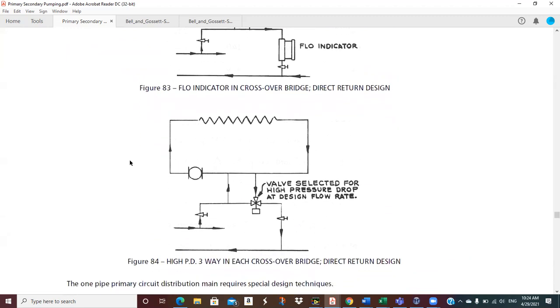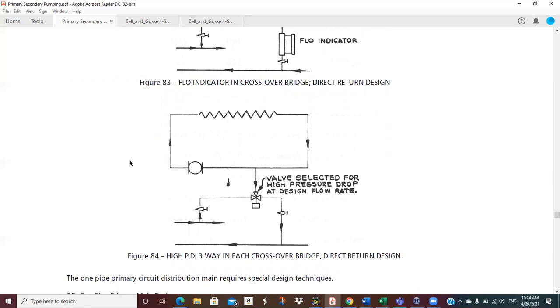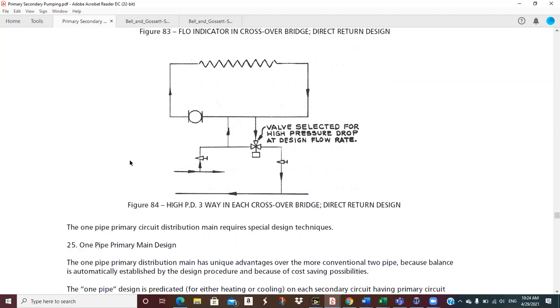And the other thing you can do is you can select that control valve in the crossover for a high pressure drop compared to all of the circuits. So say one circuit might be 10 feet, the other circuit might be 50 feet, but if I put a 50-foot control valve in there, I reduce the percent difference between them, which makes it easier to balance. Now you'd have to run the numbers before you decided whether that was a good idea, because that's extra head that your primary pump is going to see, because that's in the crossover. So that may or may not be a good idea.